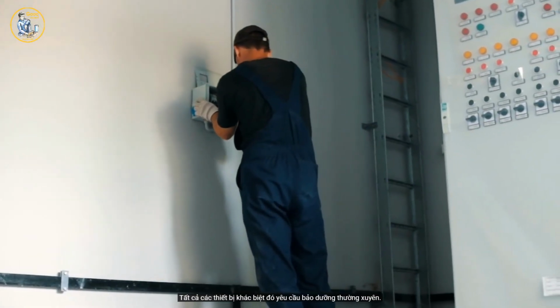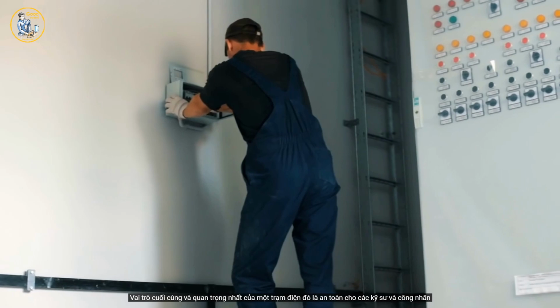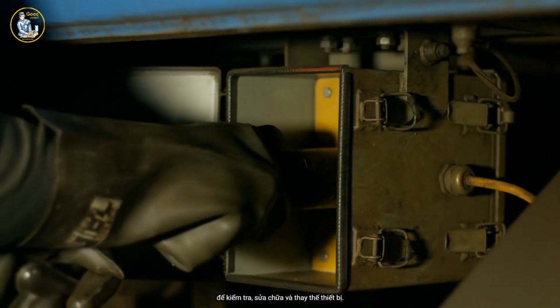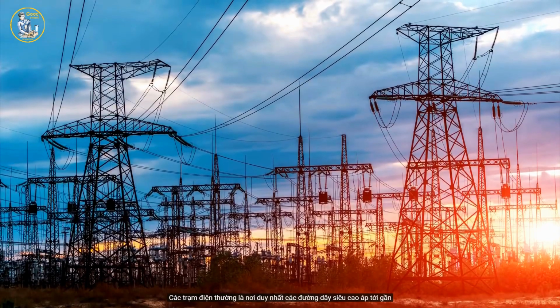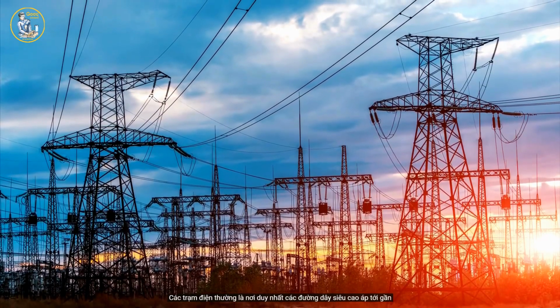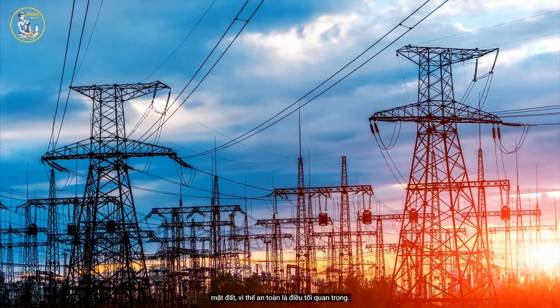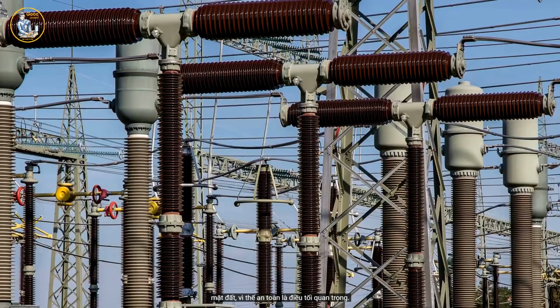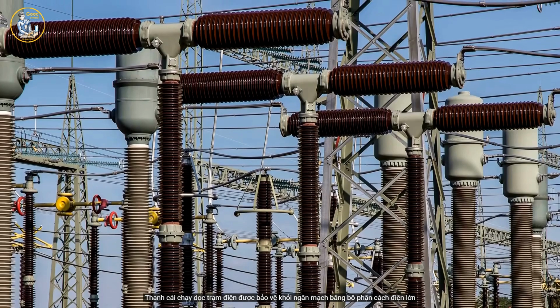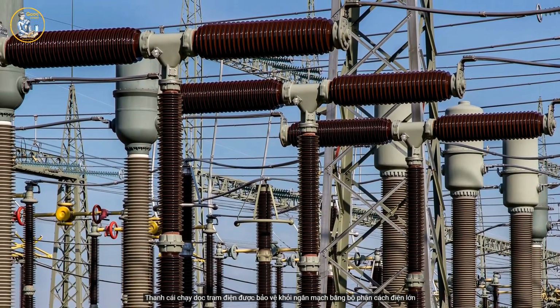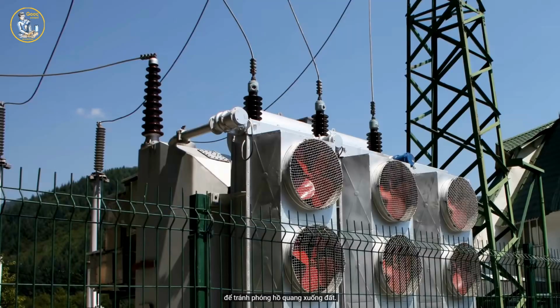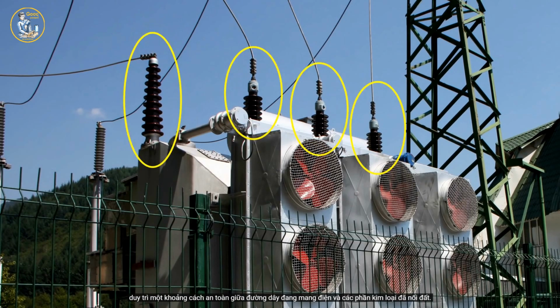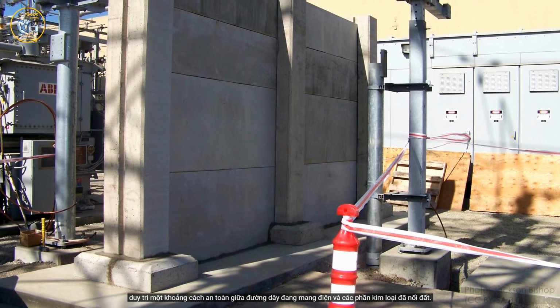All that different equipment requires lots of maintenance. The final and most important role of a substation is that it be safe for electricians and linemen to inspect, repair, and replace equipment. Substations are usually the only locations where extra high voltage power lines get close to the ground, so safety is absolutely critical. The buswork running along the substation is protected from short circuit by large insulators to avoid arcs to ground. Even the connections into each piece of equipment are done through a device called a bushing, which maintains a safe distance between energized lines and the grounded metal housings.